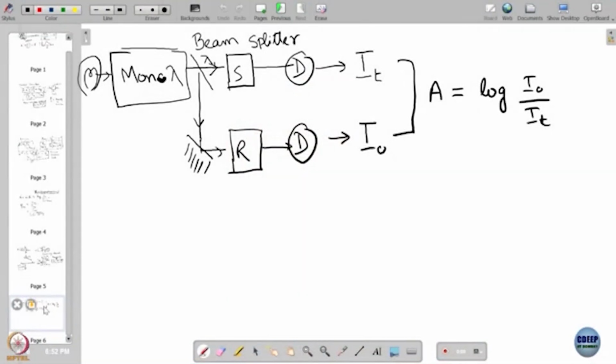So, in a typical absorption spectrophotometer, you do not really care about the intensity that is going through, because in any case you are going to take a ratio. So, you want to record a small slit width. The delta lambda I was talking about, the range of wavelength that gets through, is typically called bandwidth. The most usual value for an absorption spectrophotometer is 2 nanometer, but sometimes you might need more accuracy. So, some spectrophotometers have variable bandwidth, can go from 0.5 nanometer to higher.